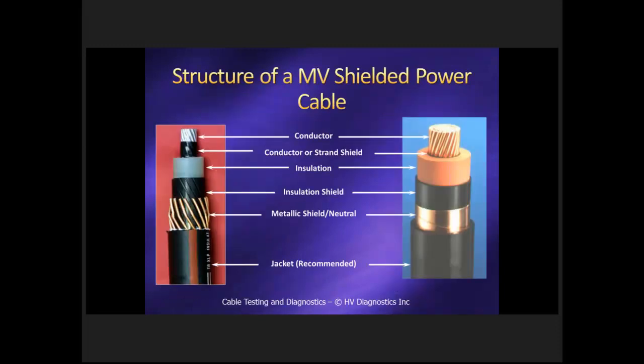To understand any form of testing on a cable, doesn't matter if it's purely high voltage testing, diagnostic testing, which could include tan delta or partial discharge, or a host of other diagnostic techniques, you need to understand the construction of a cable. And if you look at the construction, there needs to be a clear understanding of what the different components are and what are their purpose. So obviously the first part is the conductor, which conducts the current down to the load.